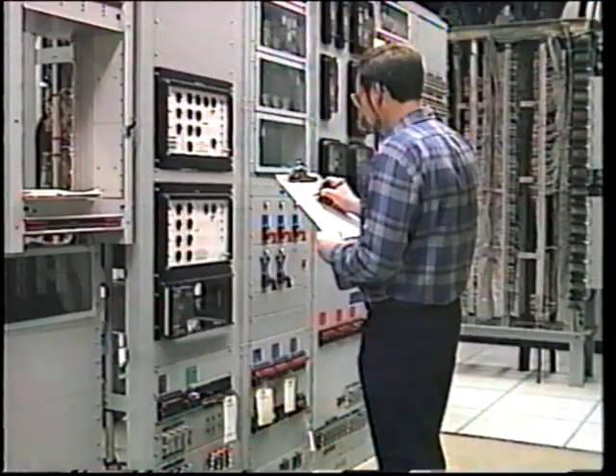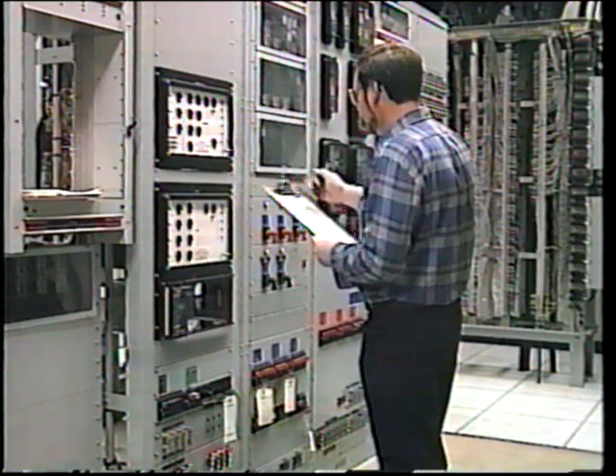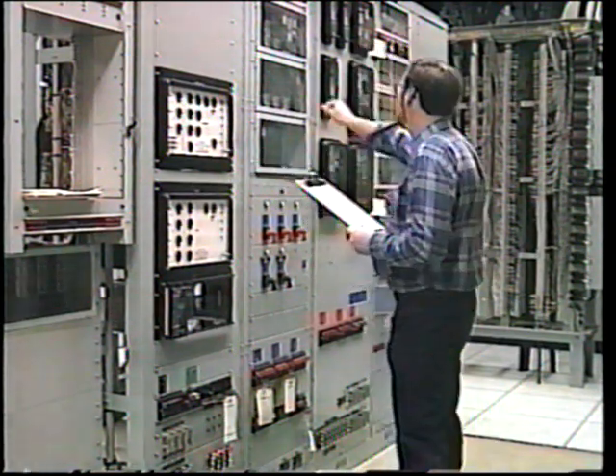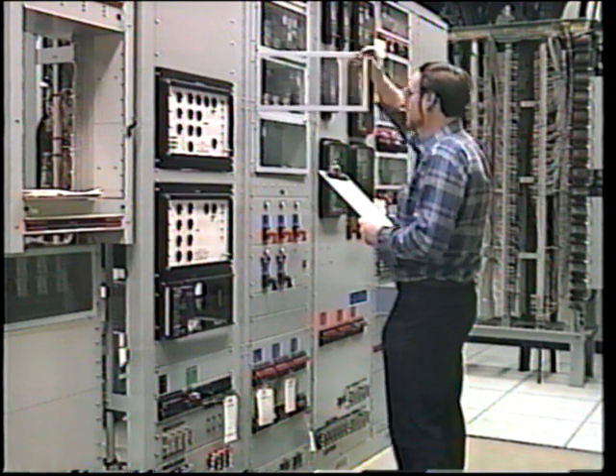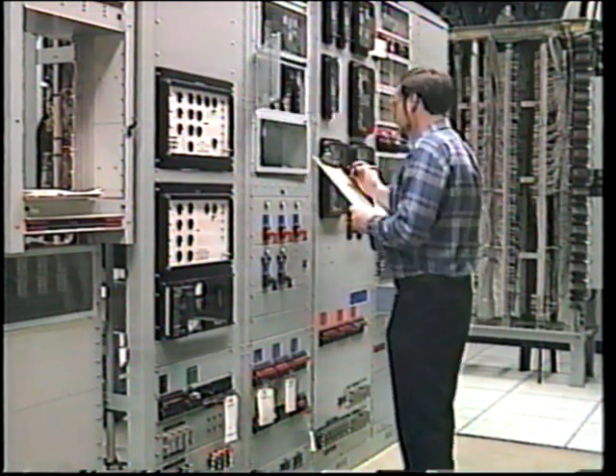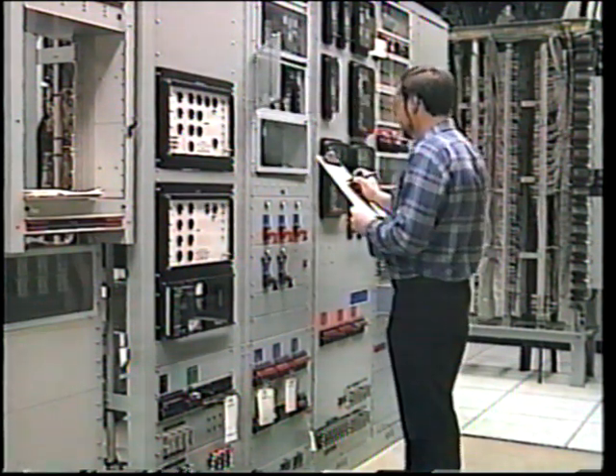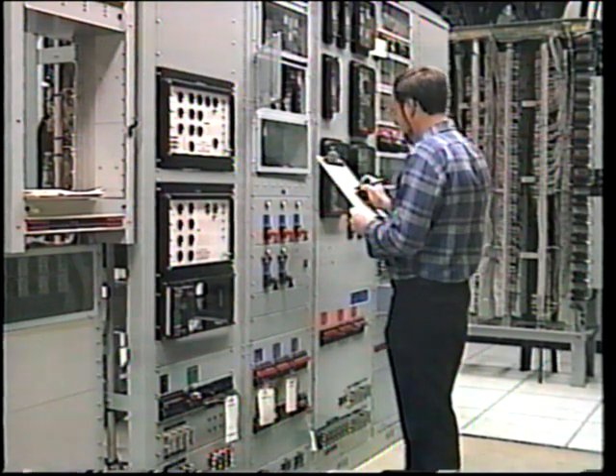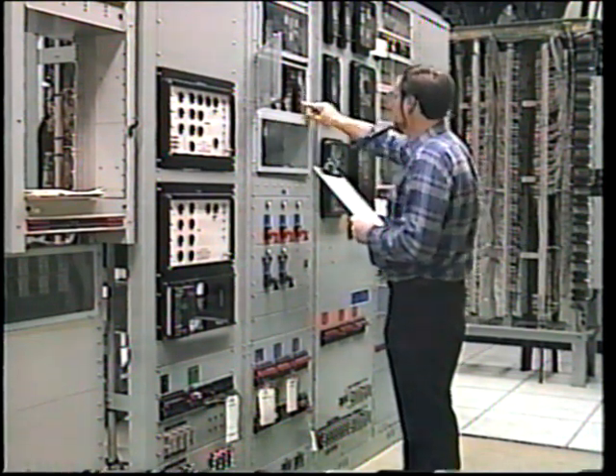The incidence of faults on the power system is in fact quite rare. Now, I know it doesn't seem this way when we're called out to attend various problems during a heavy storm, but it is true that most of the protection equipment is rarely called upon to operate to clear a fault. And yet, when a protection scheme is required, it is vital that it operate reliably with perfect sensitivity and selectivity.